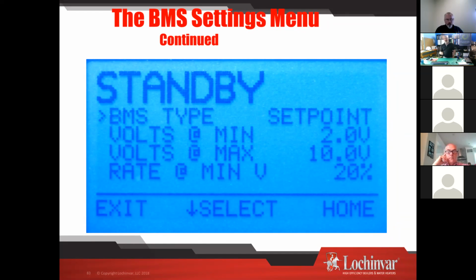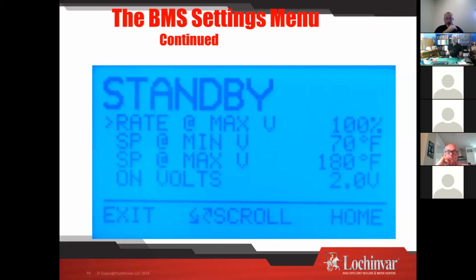Generally, you want to stay away from telling the boilers a firing rate, because that's what they do, and it overrides a lot of their internal logic sometimes. But set point is always the way to go. Just give it a set point demand. Okay.